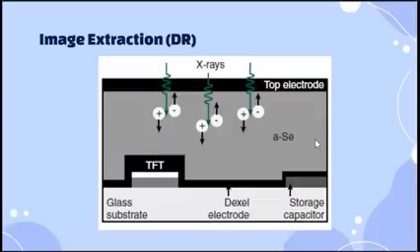In direct radiography, it's called direct because there is no need for a scintillator to convert X-rays into light and then light again into electrical charge. Here it is direct, X-rays to electric charge. X-rays or light rays penetrating into this layer of selenium ionize its molecules.